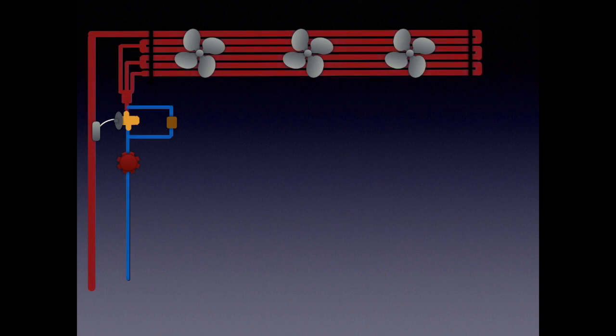So you see we kind of changed some things there. The vapor went back through the evaporator and it kind of condensed into a liquid. Now that liquid bypasses the metering device, runs through that check valve that we talked about earlier, back to the liquid line.